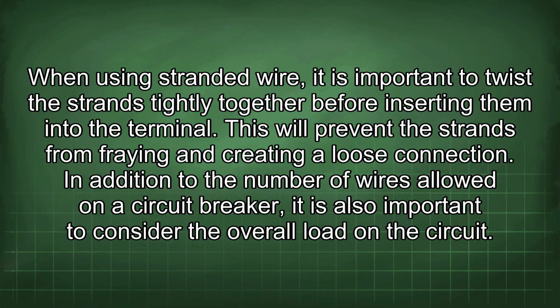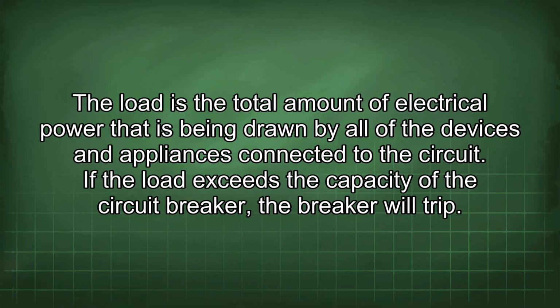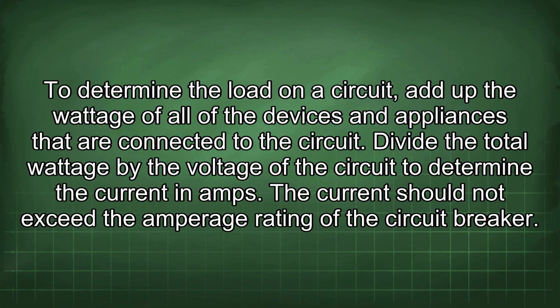In addition to the number of wires allowed on a circuit breaker, it is also important to consider the overall load on the circuit. The load is the total amount of electrical power that is being drawn by all of the devices and appliances connected to the circuit. If the load exceeds the capacity of the circuit breaker, the breaker will trip. To determine the load on a circuit, add up the wattage of all of the devices and appliances that are connected to the circuit. Divide the total wattage by the voltage of the circuit to determine the current in amps. The current should not exceed the amperage rating of the circuit breaker.